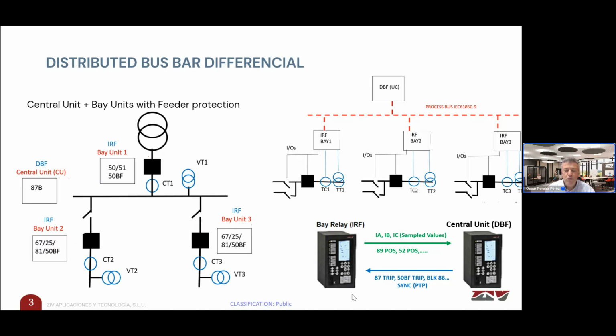If we move to the right side of the slide, I started this presentation saying that our Busbar differential protection works under 61850 using the process bus.